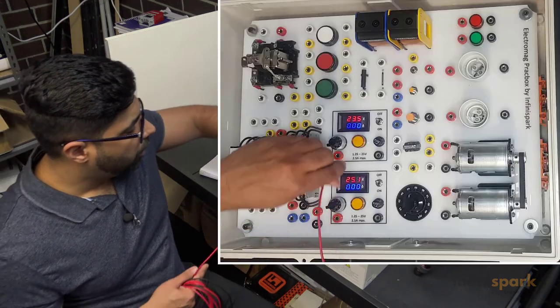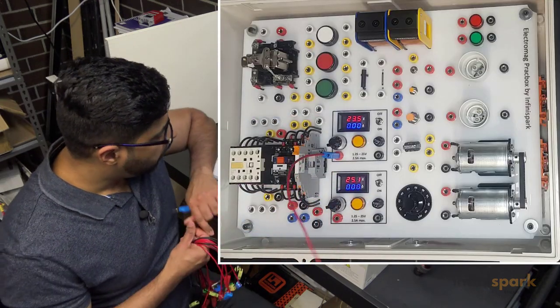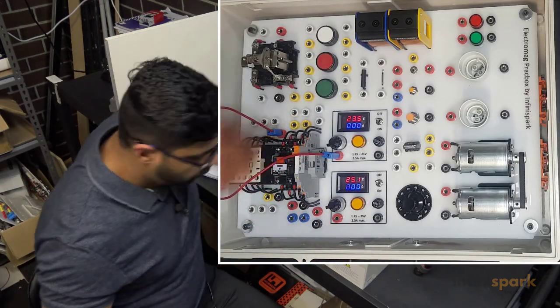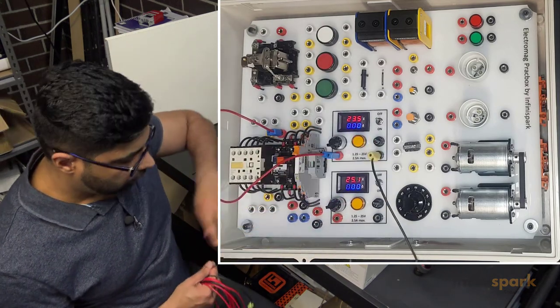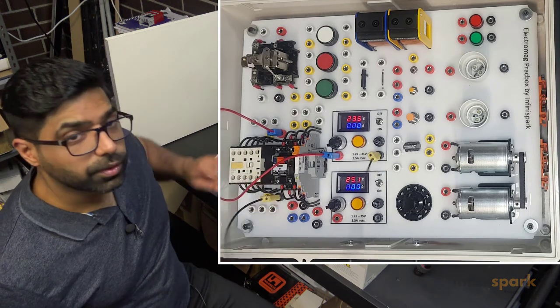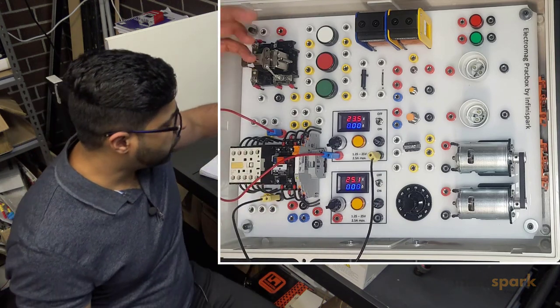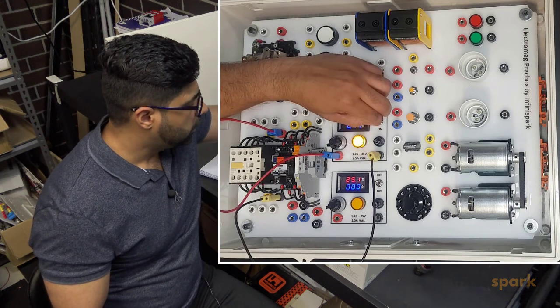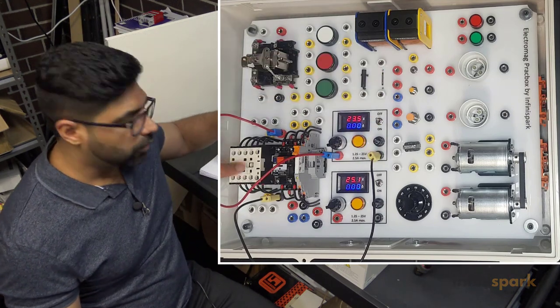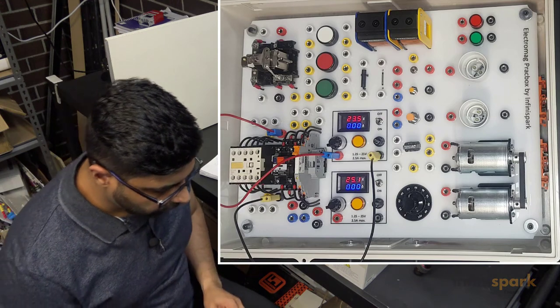Positive of my power supply goes to positive of the contactor, and negative goes to the negative side of the contactor coil. Let's turn it on to test if we wired it correctly. We can see how this contactor turns on when I turn that on, so that's wired correctly. That's the control circuit.